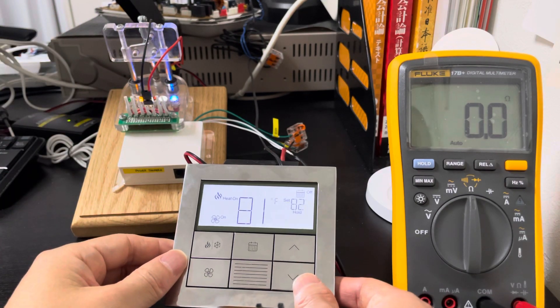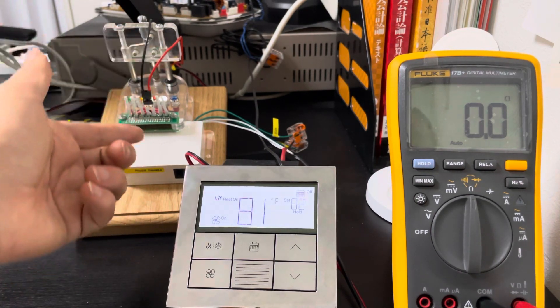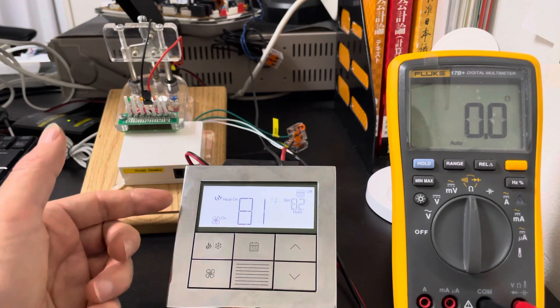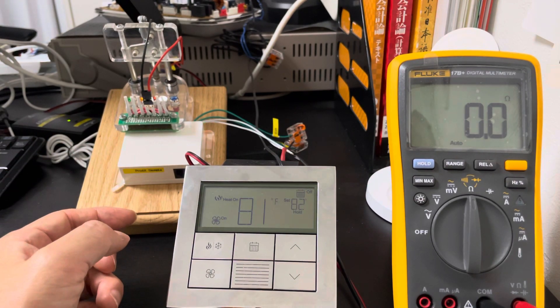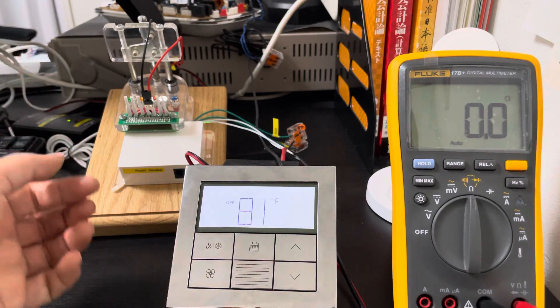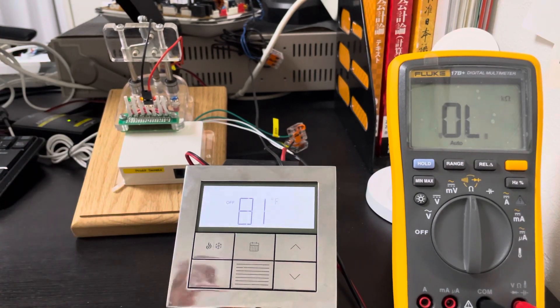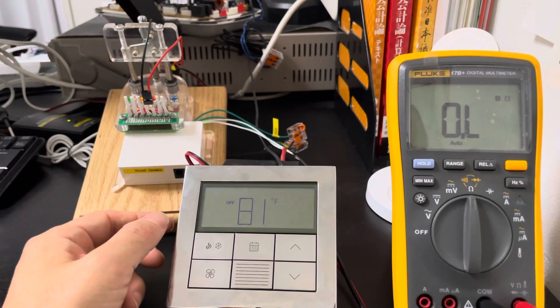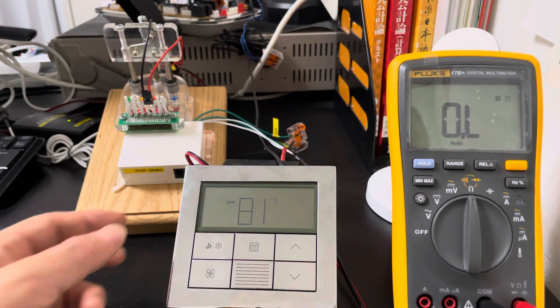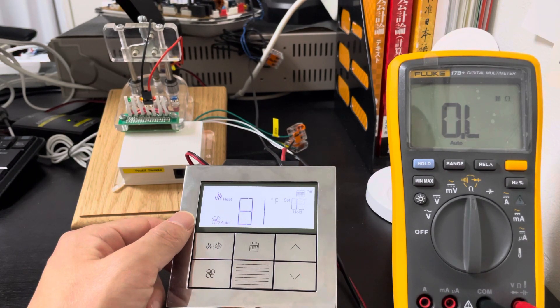When it reaches the touch temperature it will turn off, and when it begins heating again it only uses the in-floor heat. This means the in-floor heat is the main heat source and the FCU heat is the temporary source. On another side, we can turn off the ventilation and in-floor systems and use FCU heat and in-floor at the same time always.